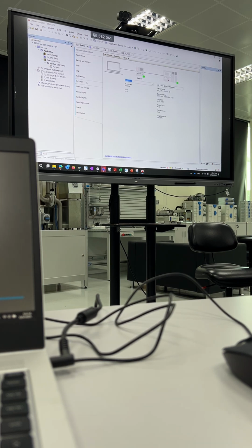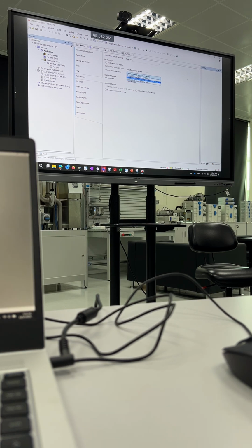Then one thing that I would always do is in terms of the PLC settings. If the I/O device is not used in the bus cycle, like if it's configured currently like this, there could be times when you won't be able to read the I/O device. So what I will normally do is update the I/O and set it to enable one, so it will be used in the bus cycle task. If it's not used in any task, for the bus cycle task we just use the main task, or it could also be your EtherCAT task.